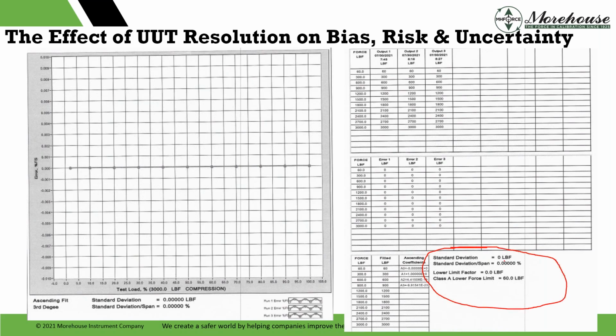Lower limit force factor, the LLF, that's what you calculate when you do an ASTM calibration. That's 0. Class A 60 pounds. So with coarse resolution, everything repeats perfectly. Some people might be saying, hey, I get a great calibration that way. You do not. This is just an example of not accounting for it. Since it's so coarse, it's not detectable.